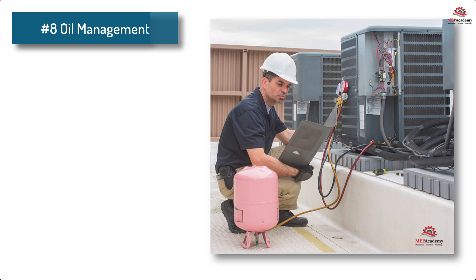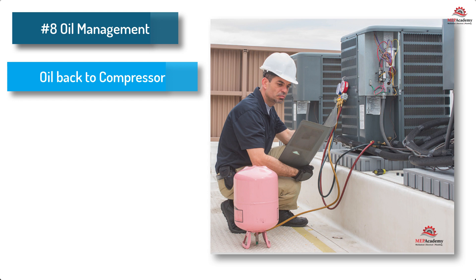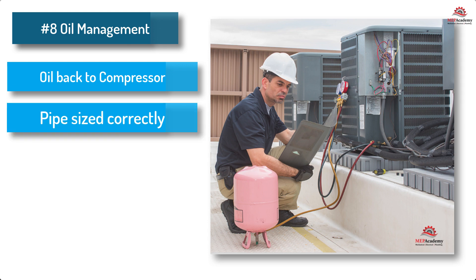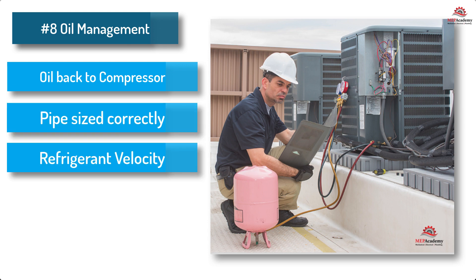8. Refrigerant oil management. Oil will be circulated around the system with the refrigerant and must be returned to the compressor, where it's needed to provide lubrication of bearings and moving parts. For this to happen, it's important that the refrigerant piping is sized correctly, including the refrigerant velocity. As refrigerant changes from a liquid to a vapor in the evaporator, the oil is separated out, which requires the correct velocity to ensure that the oil returns to the compressor at the same rate at which it leaves.